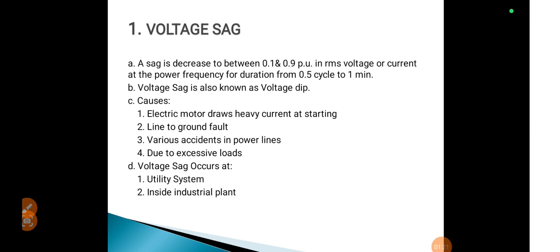The most common power quality issue is voltage sag. Then what is voltage sag? The decrease in voltage is called a voltage sag. A decrease or dip in voltage is called a voltage sag. A decrease of the normal voltage level between 10 to 90% of the nominal RMS voltage at the power frequency for a duration of 0.5 cycle to 1 minute is called a voltage sag.